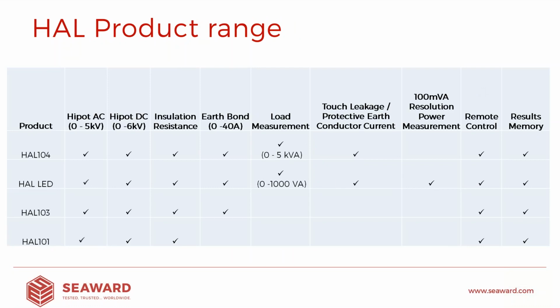As you can see on the table, all of our testers in the HAL series will perform AC high pot at 50 or 60 hertz, a DC high pot, and an insulation resistance. For those that need tests that are earth or ground bond for their equipment, the HAL 103 adds that feature. In addition to traditional safety testing, our HAL 104 and HAL LED also adds the ability to perform load and leakage testing, ideal for those who also want to ensure the product is fully operational prior to shipping, potentially saving on expensive out-of-the-box replacement costs. The HAL LED is perfect for manufacturers of low power products who want the flexibility to perform operational checks, and is ideal for the LED lighting industry.